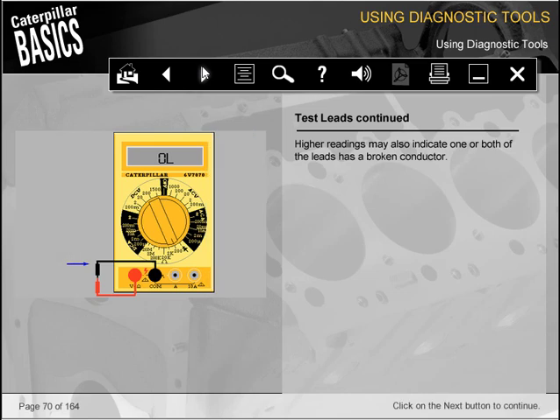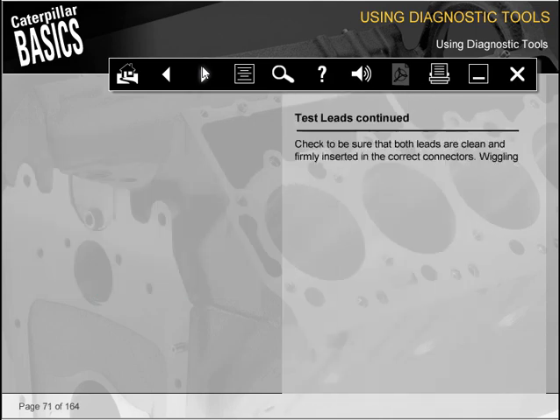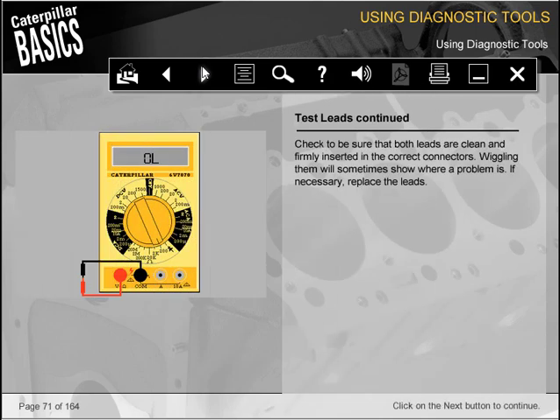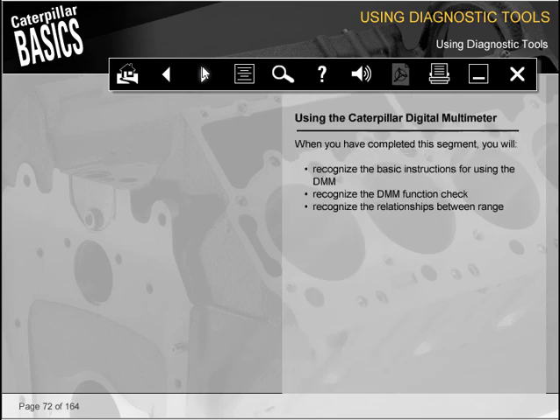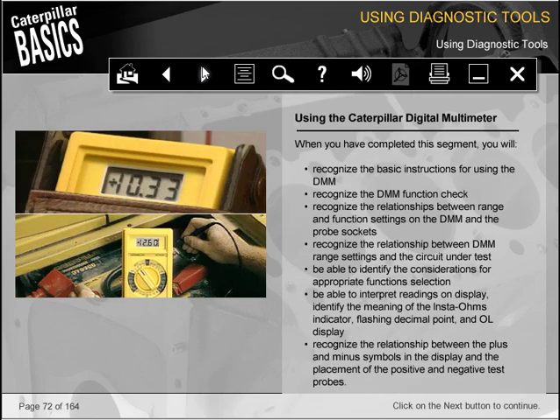Higher readings may also indicate one or both of the leads has a broken conductor. Check to be sure that both leads are clean and firmly inserted in the correct connectors. Wiggling them will sometimes show where a problem is. If necessary, replace the leads.